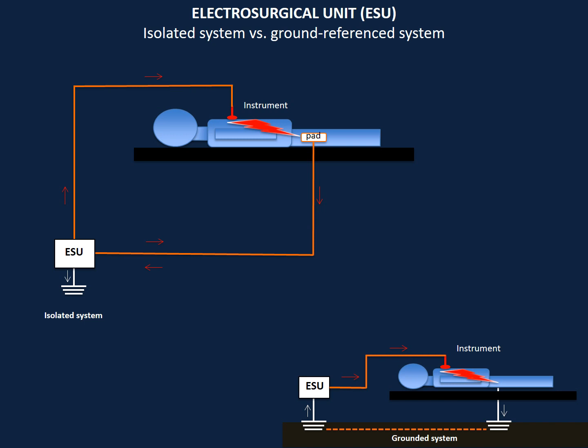With the old units, once the current enters the patient's body, it passes into the ground rather than back to the unit. The ground was an inherent part of the circuit, and the system was called a ground reference system. With the advent of isolated generator technology in the 1970s, the circuit is now completed by the generator and not by the ground. The unit recognizes the patient's return electrode as the preferred pathway back to the generator.